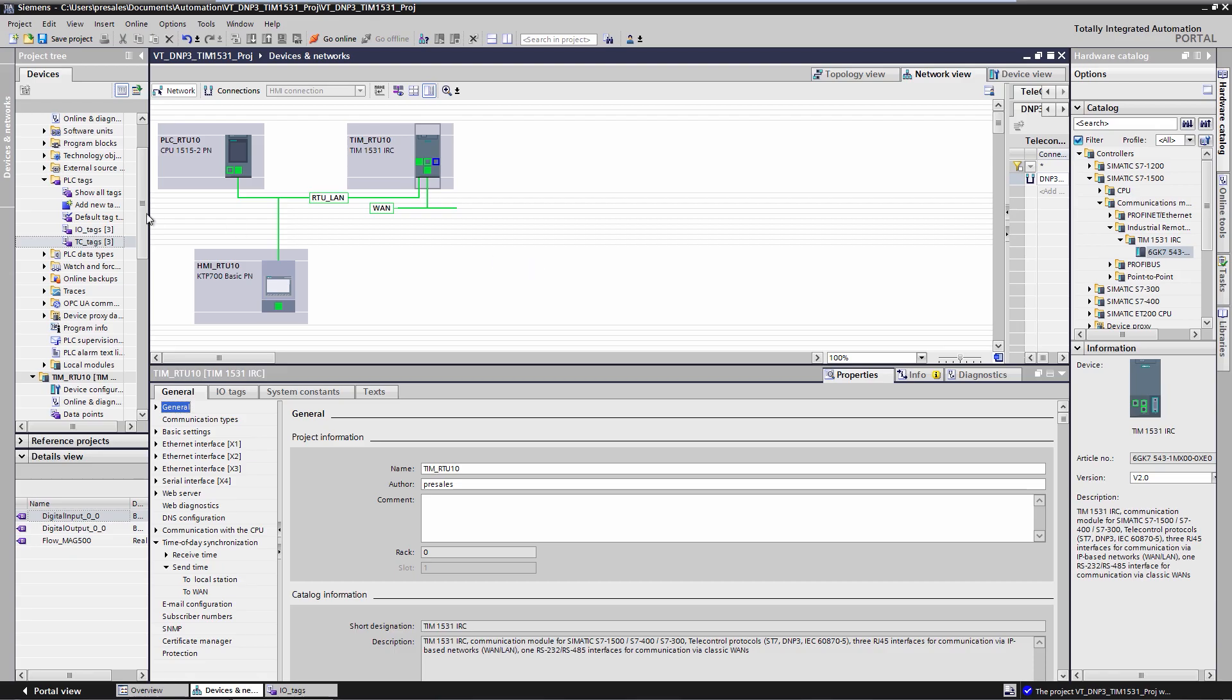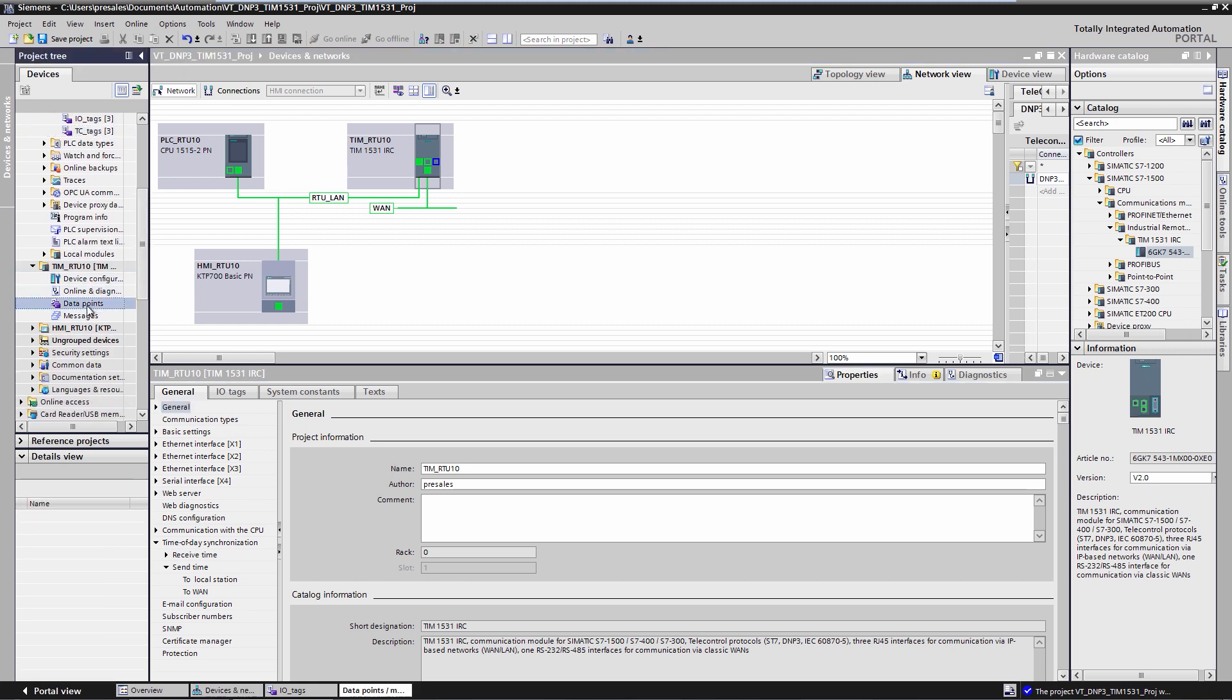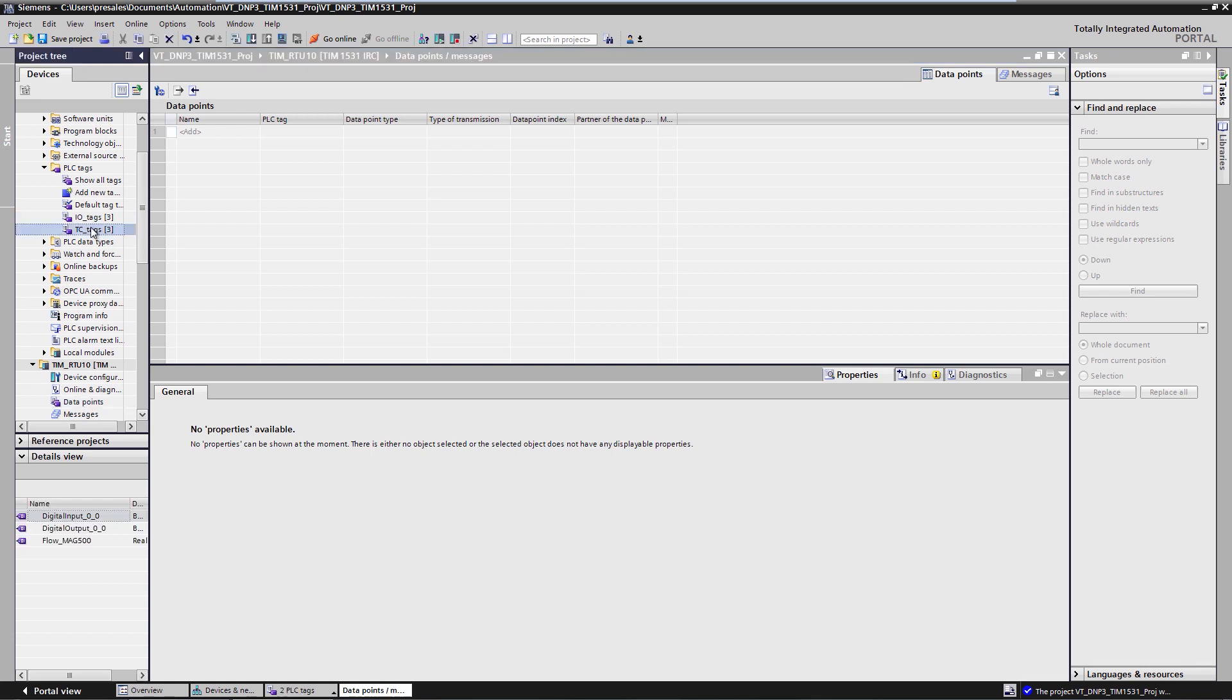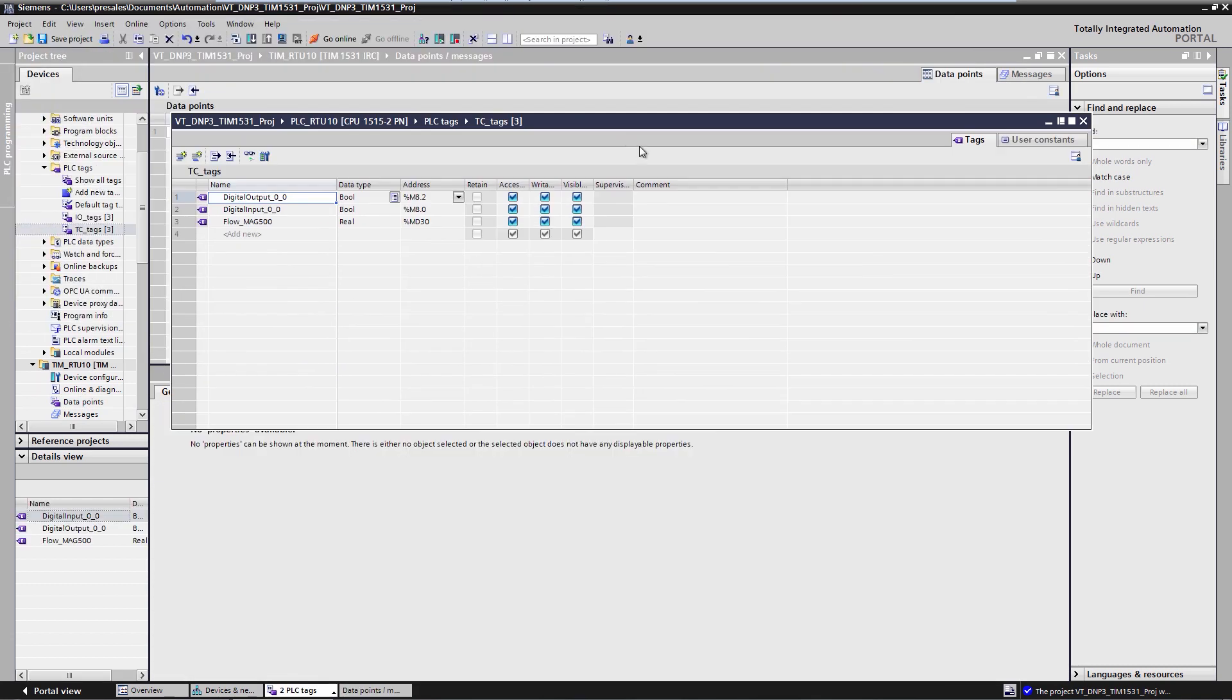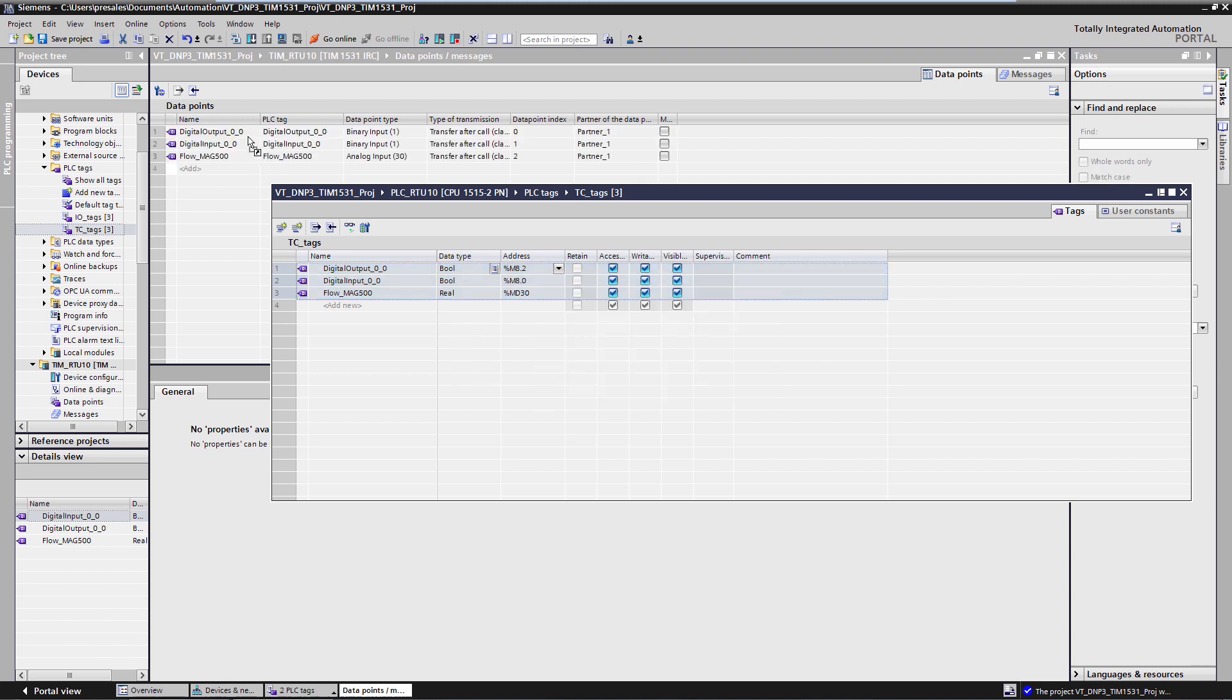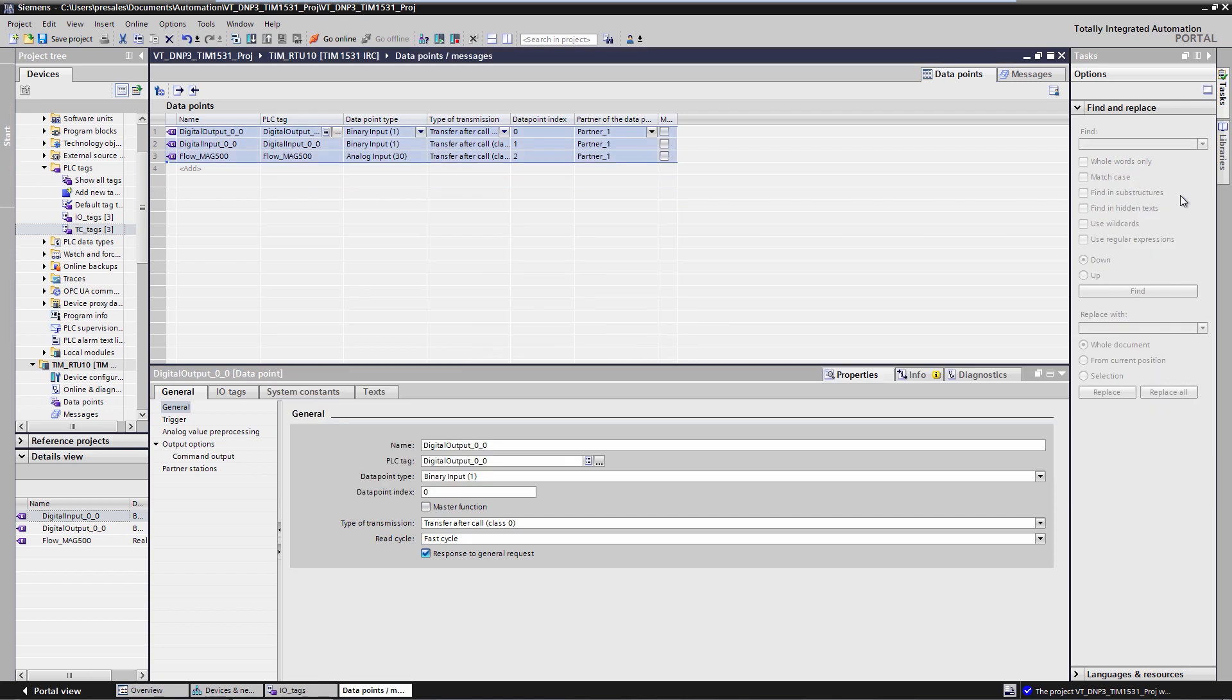A data point can also be a command or set point value sent by the master to the RTU. We now switch to the data point editor of the TIM 1531. I open the tag table or the DB on the CPU. I simply drag and drop the CPU tag that is to be sent to or received by the DNP3 master into the data point editor. Thus, the process values are transmitted on those tags as DNP3 data points from RTU to master or from master to RTU.